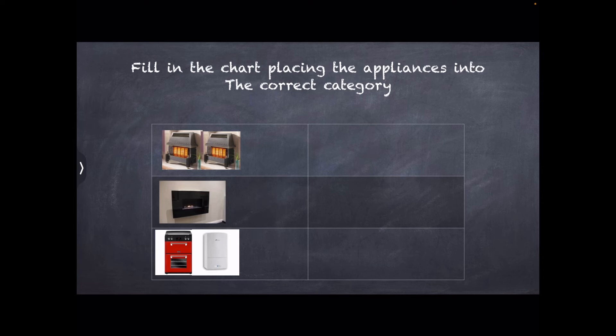Then you simply work out the ventilation requirements for each category. So in this case, we've got two six kilowatt fires. Six plus six is 12. Minus seven equals five. And you simply multiply that number by five to get the ventilation requirements: 25 centimeters squared. If you don't know how to do this, I've got other videos explaining how you ventilate these different types of appliance.